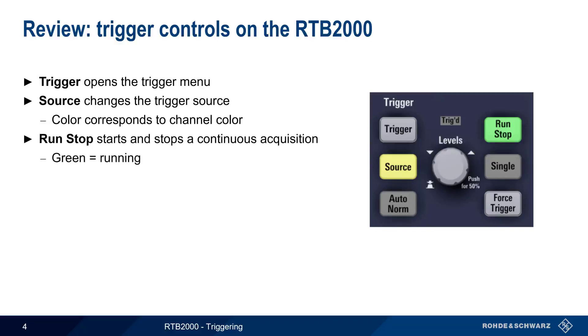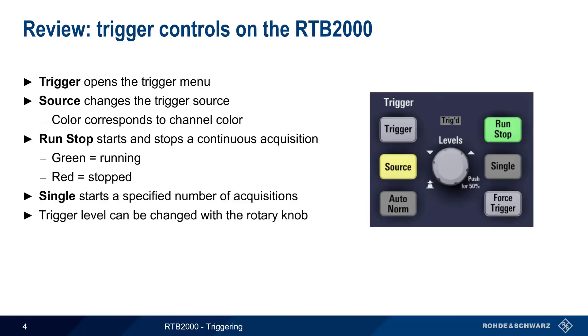The single button is used to start a specified number of acquisitions and then stop. Many triggers are based on the level of the signal, and the trigger knob can be used to manually set these levels. Note that pressing the knob sets the level to 50% of the signal amplitude, which is often a good starting point.